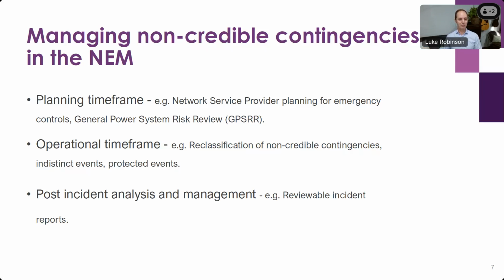We also do have in the NEM a relatively new framework as of March, which allows for us to declare what we call an indistinct event. So that's where there are conditions that could impact the power system where we can't identify the specific asset that would be impacted. So we can't say it's line 1 or line 2. It might be any one of 10 lines that could be impacted by a particular event, whether it's a geomagnetic storm, a lightning storm, or other event. And we can take measures to operate the power system to bolster its resilience in real time.